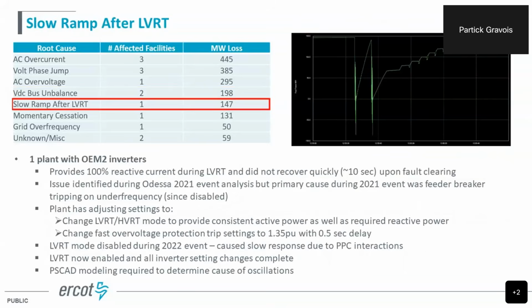Back to what we're calling a slow ramp after a low voltage ride through. This is a single plant, an older plant. Last year it tripped on the feeder breaker on underfrequency. They disabled that, but this is a plant we have been working with throughout the past year. They were in the process of increasing some settings.